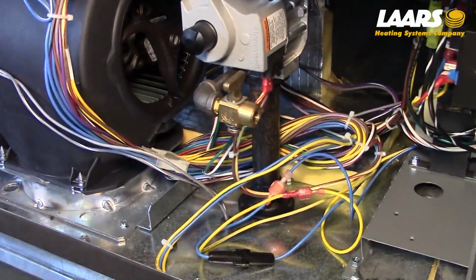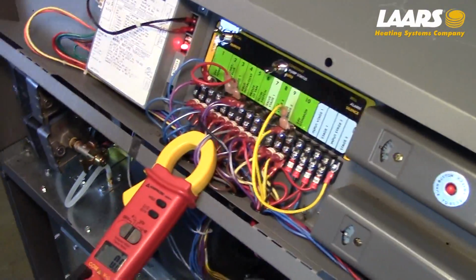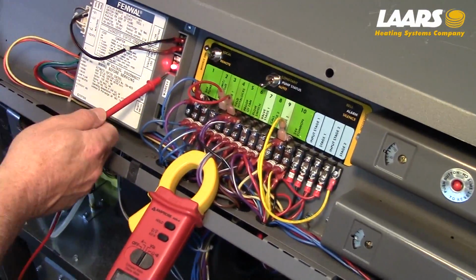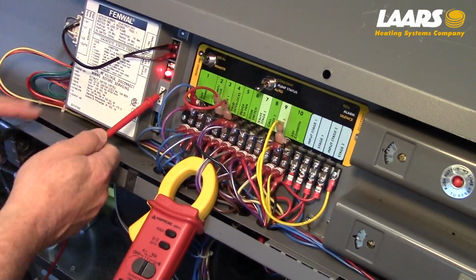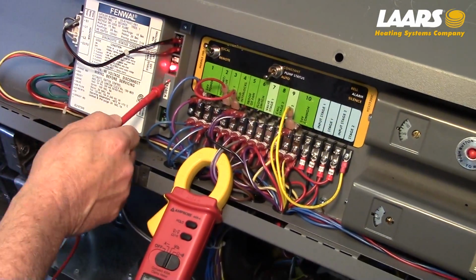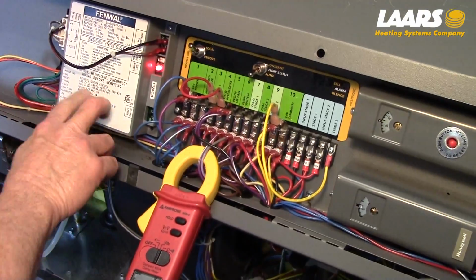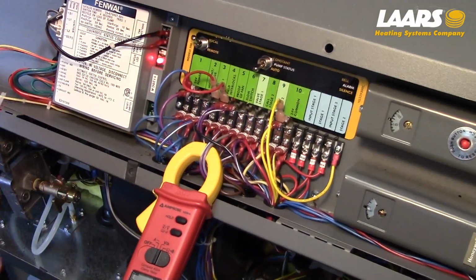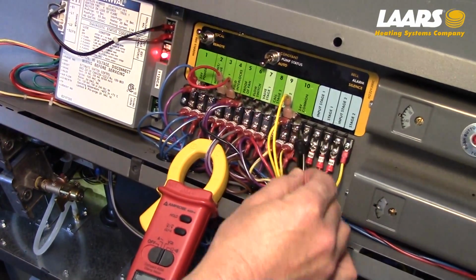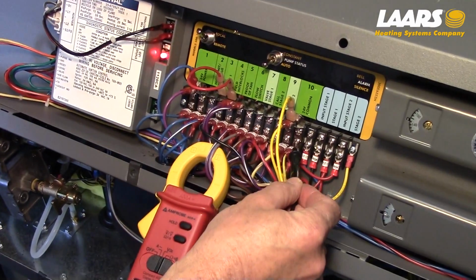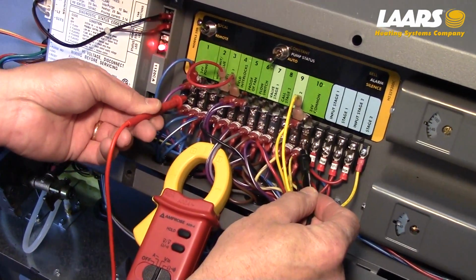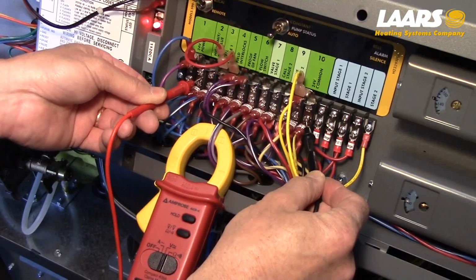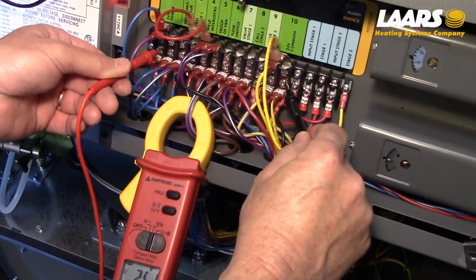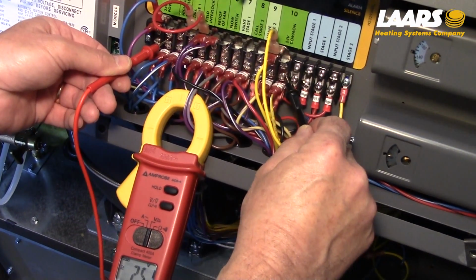And now we're going to go back to the terminal strip, and I also want to show you, now you can see there's an LED light here on the Fenwal ignition control. So I know I have 24 volt power, but we're going to check it anyways. Start with 1 meter lead on 24 volt common. Over here I can either go to terminal 1 or terminal 2. You can see I'm reading 25.1 volts on either one of these terminals.